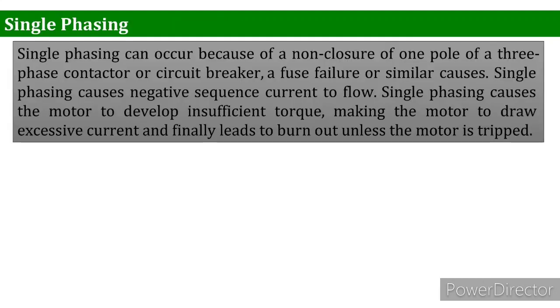Next one we have is single phasing. As we all know, single phasing can occur because of non-closure of one pole of a three-phase contactor or a circuit breaker. Single phasing causes negative sequence current to flow. It causes the motor to develop insufficient torque, making the motor draw excessive current, and finally leads to burnout unless the motor is tripped.